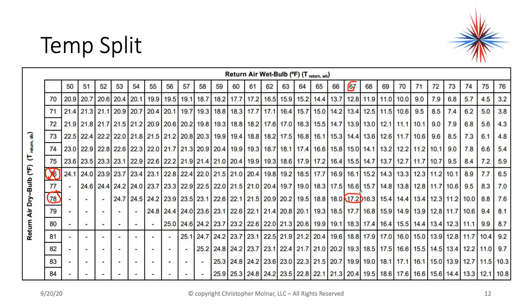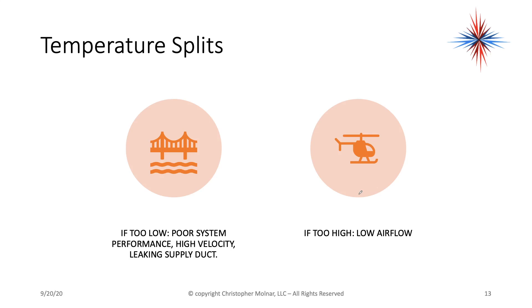If the temperature split is too low, we have poor system performance — we could have high air velocity, in other words air moving across the coil too fast, which could lead to a leaking supply duct. If it's too high, which is where we're at, we have low air flow. The longer the air sits on the evaporator coil, the colder it's going to get.